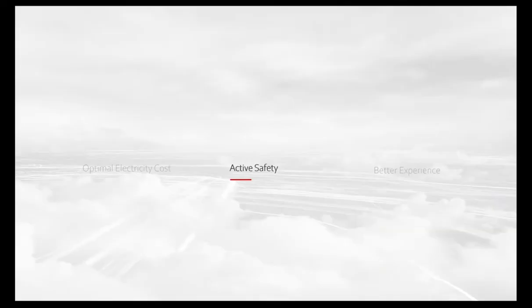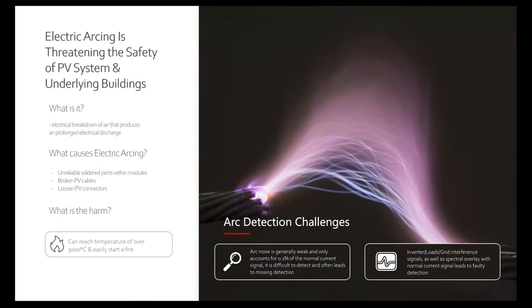So another factor for the C&I applications is the active safety. Now, we all know with an electrical system, the hazards are substantial. We need to first of all understand where the hazard points are on the PV applications. So first of all, we need to be looking at the unreliable soldering joints within the PV modules due to potential quality issues. Second of all is the broken cables that are potentially affected over the aging of the project itself, and then loose PV connectors, potentially by the installer or by not correctly terminating them into the inverters, etc.